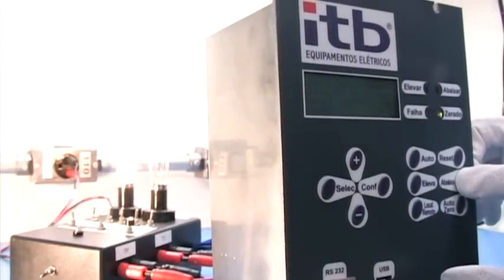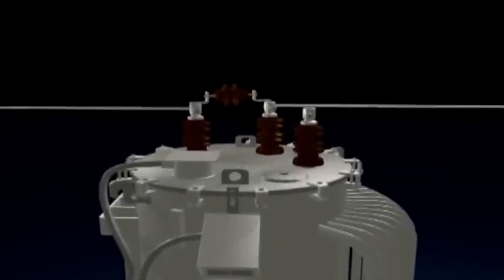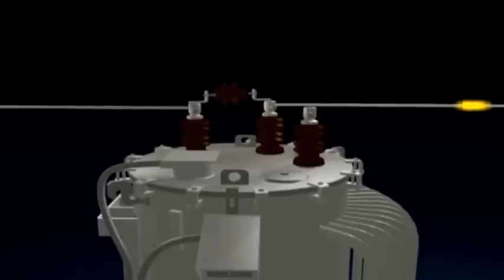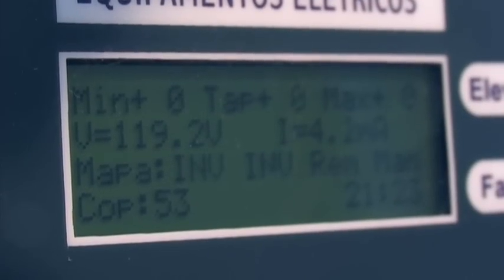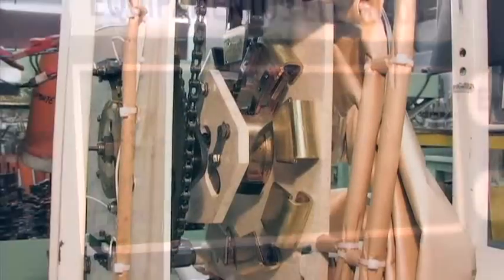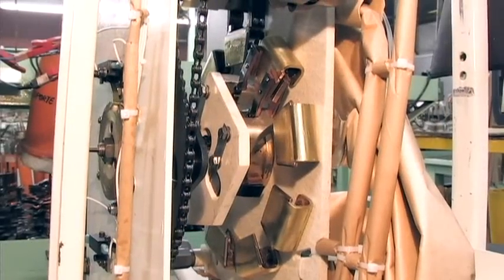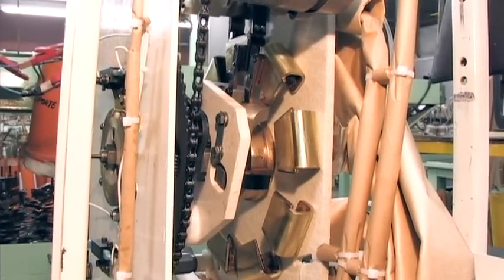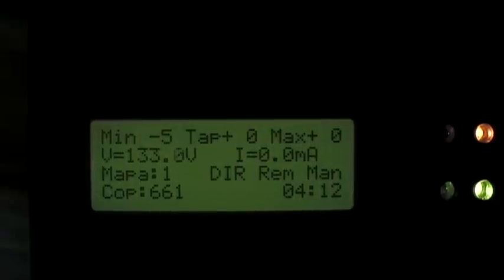Reverse and direct power flow capability without any special transformer for this purpose, except in the case of closed delta connection, when reverse power flow is determined by switching between substations within the same electric grid. An auto zero function, which reallocates the on-load tap switcher to a neutral position from any other one.